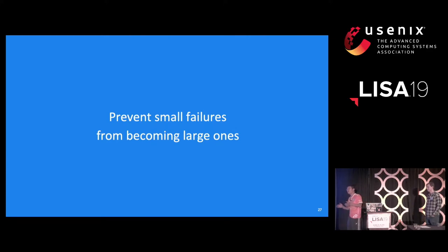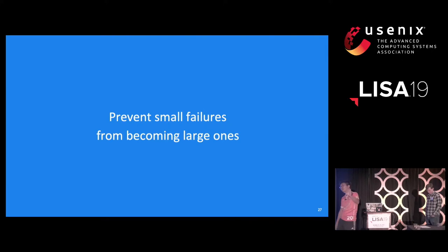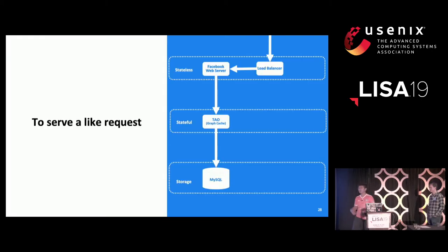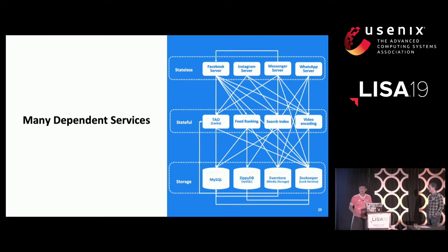We must be able to prevent small failures from becoming large ones. This problem is actually pretty simple if you think about it: I have a switchboard powering a lot of MySQL servers, and another powering a lot of TAO servers — why can't TAO and MySQL just swap their machines so each one has a smaller amount per switchboard? But there are a couple of challenges: to serve a like request you need four services, but to serve Facebook, Instagram, Messenger, and WhatsApp there are thousands and thousands of services needed.